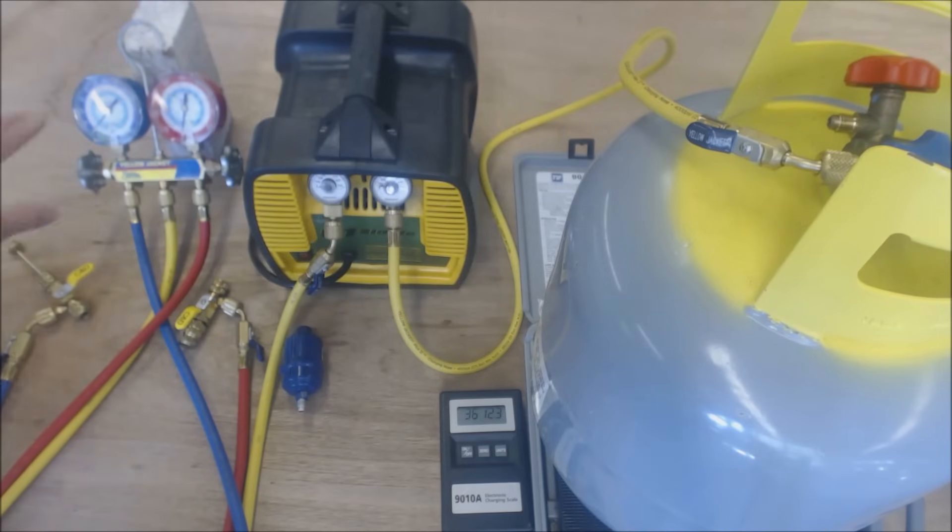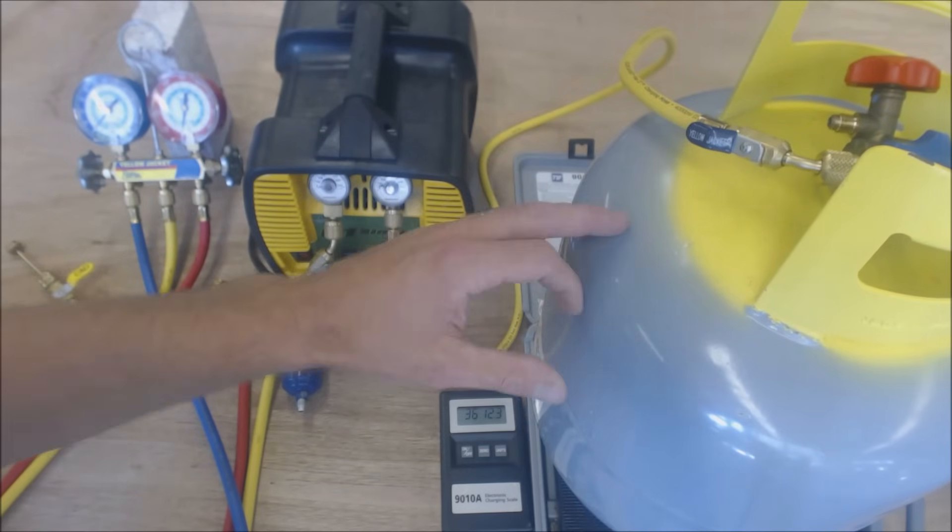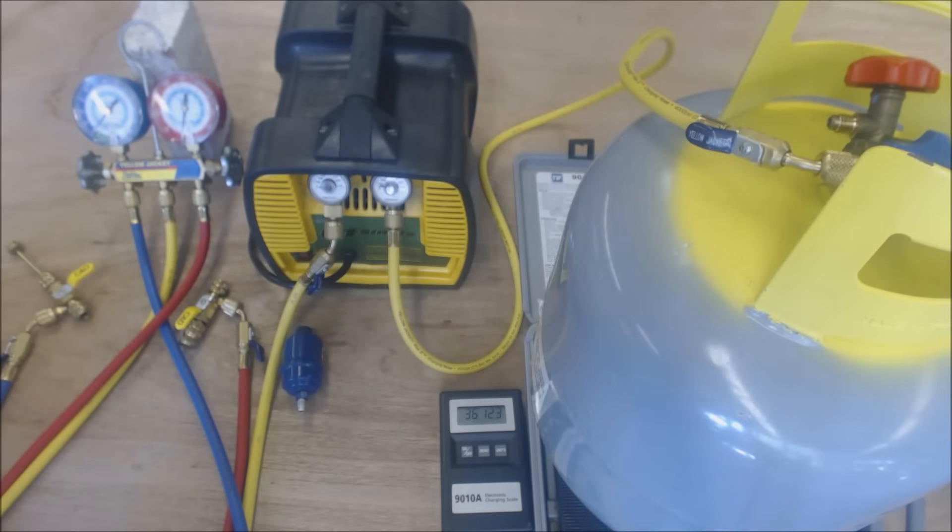For HFCs like 134A and R-410A, you pull them down to 10 inch Hg. For R-22, if the system's below 200 pounds, you're going to pull that down to zero. You can check out your guidelines on that at EPA.gov just to verify those things.